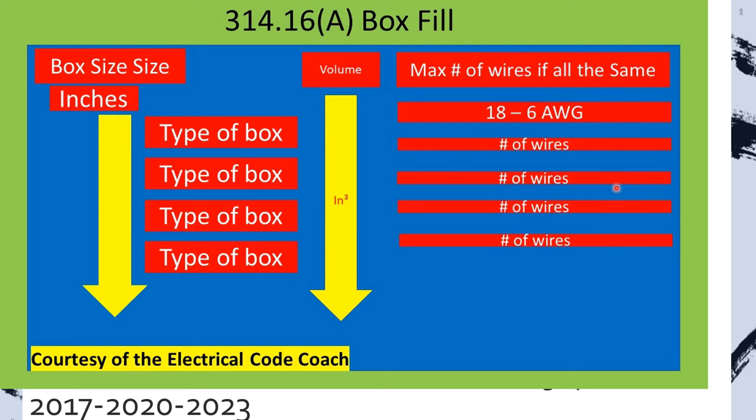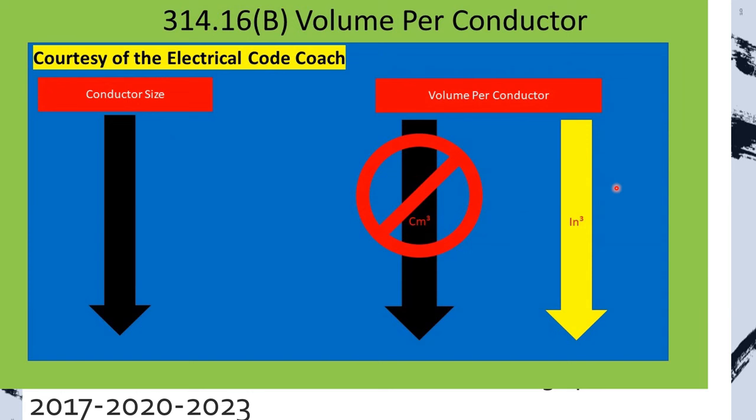Now let's look at the second table that we're going to be dealing with for box fill. And it's right below there. It's 314.16b. And this one's very simple to understand. On the left-hand side is our conductor size. And on the far right-hand side is going to be our cubic inch volume.